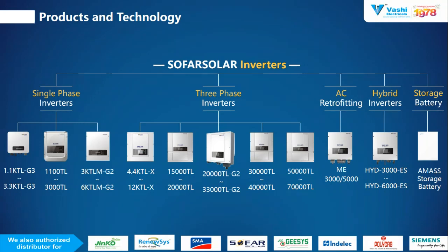These inverters are newly designed products with 2 MPPT, and per MPPT you can connect 3 strings, so a total of 6 strings. Above the 25 kilowatt G2 model, all the inverters have a fan cooling facility, and the inverters below that have a natural cooling facility.